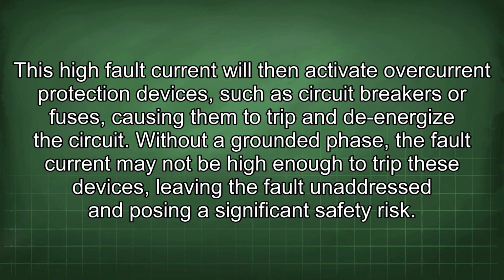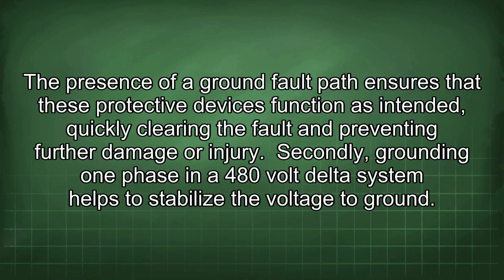and de-energize the circuit. Without a grounded phase, the fault current may not be high enough to trip these devices, leaving the fault unaddressed and posing a significant safety risk. The presence of a ground fault path ensures that these protective devices function as intended, quickly clearing the fault and preventing further damage or injury.